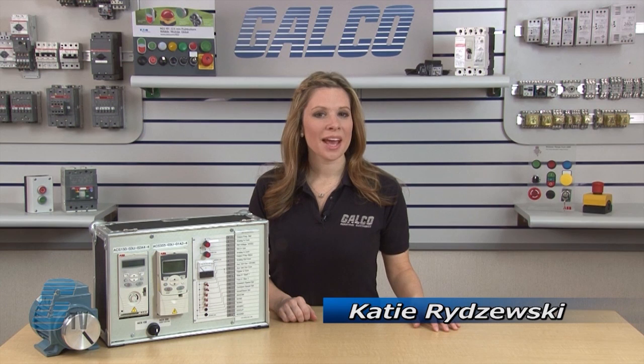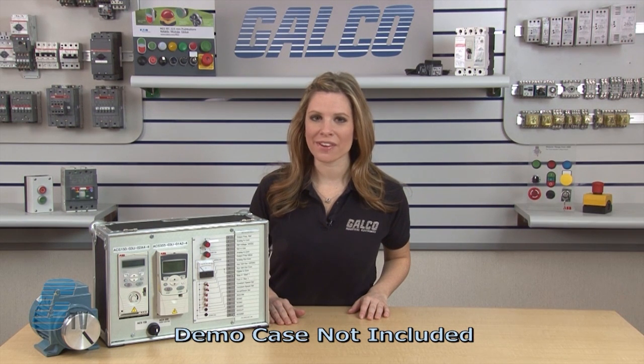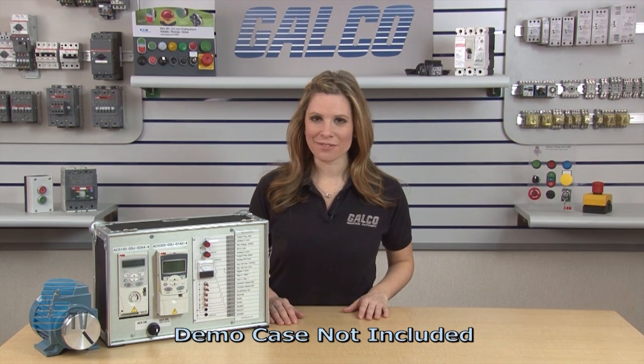Welcome to GTV. Today I would like to demonstrate how to do a basic startup and operation of an ABB ACS355 AC drive using the advanced control pad. After verifying that the wiring is correct, I can apply power to the drive to begin programming.